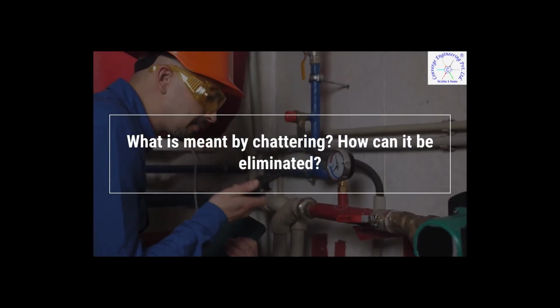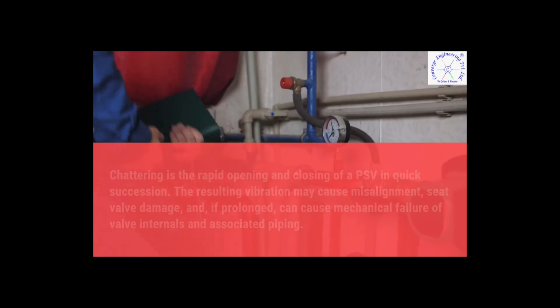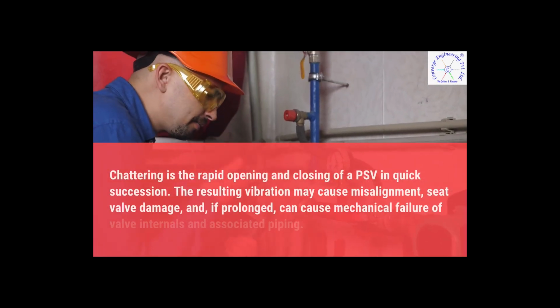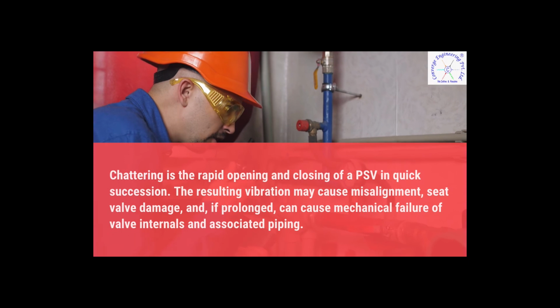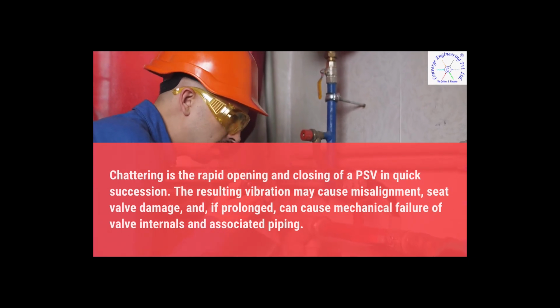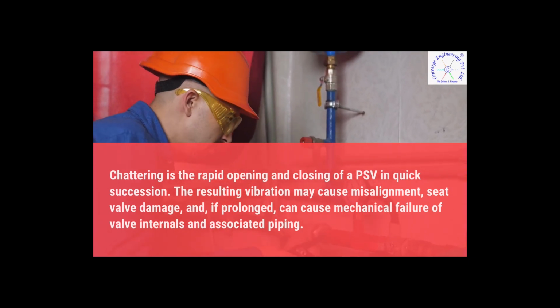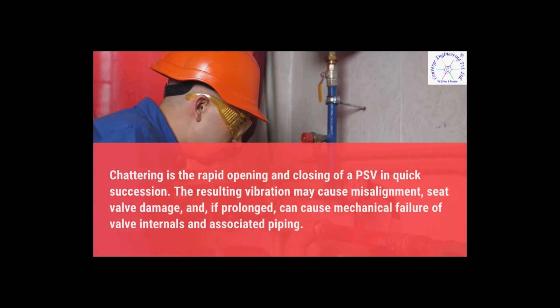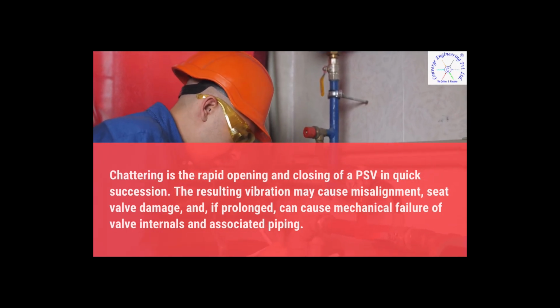What is meant by chattering? How can it be eliminated? Chattering is the rapid opening and closing of a PSV in quick succession. The resulting vibration may cause misalignment, seat valve damage, and, if prolonged, can cause mechanical failure of valve internals and associated piping.